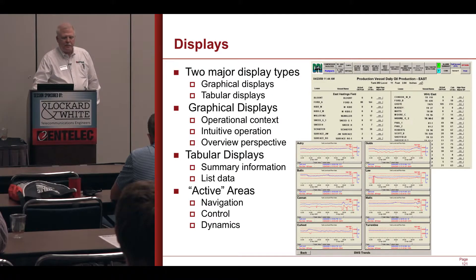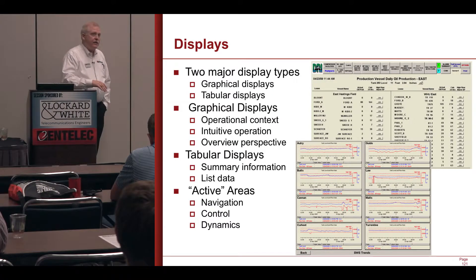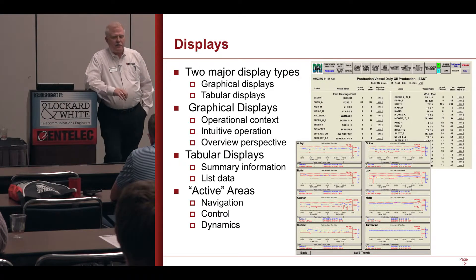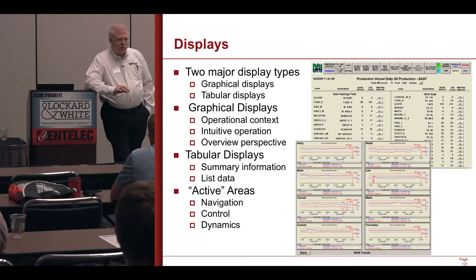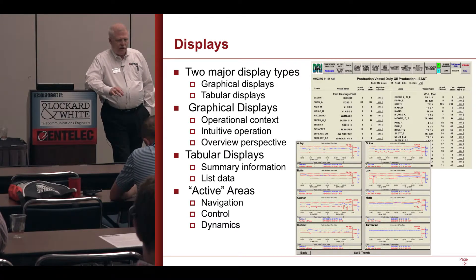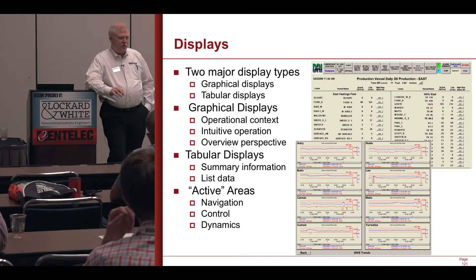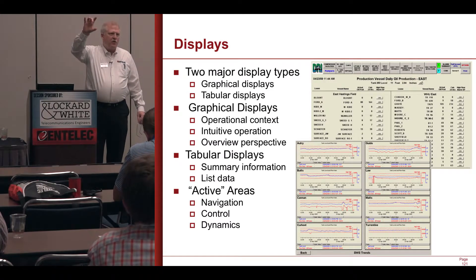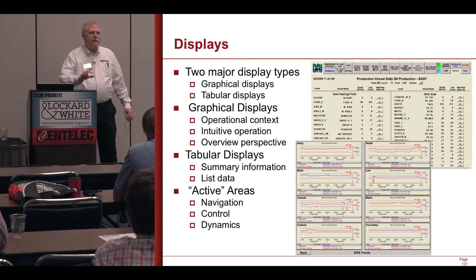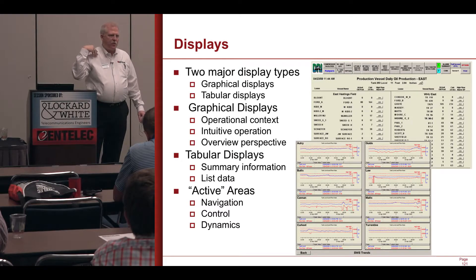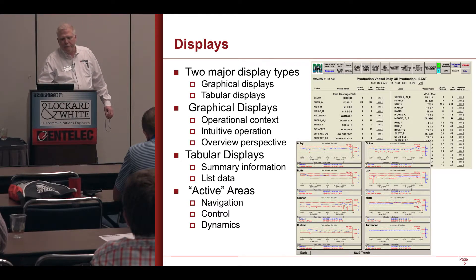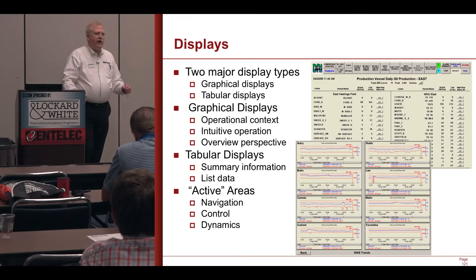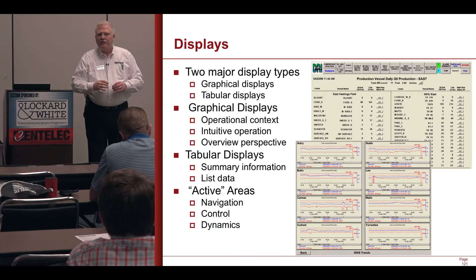There is a lot of need for displays. In the high performance HMI — and there are some good resources out there about this — less is more. Most HMIs built for process control have too much data, or the wrong data, or the data presented the wrong way. If you're going to do these HMIs well, you've got to focus on what they need to operate: what do I need to understand what's going on, and what do I need to dig down and do analysis. I've got to keep aware at any given moment whether the process I'm responsible for is normal or abnormal. If I click on something, I don't want it to pop up in a dialog and cover something else up, because I could have something alarm or go out of whack and I can't see it.